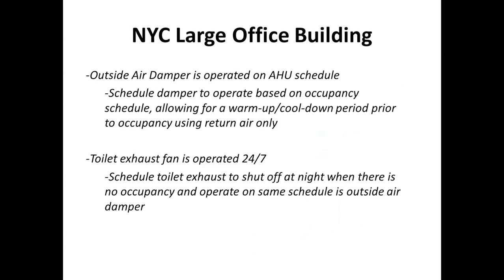Some of the recommendations we made, and these are just to highlight really common ECMs, energy conservation measures that we've been seeing in commercial buildings. In this particular building, there was a warm-up and cool-down period. The air handlers were scheduled to kick on about 2 hours before occupancy and stay on for 2 hours after occupancy, occupancy being the time when the first employee enters and the last employee leaves during the day. Although this is a good thing, the air handler was kicking on to pre-cool or preheat the building, and it was also operating the outside air damper.